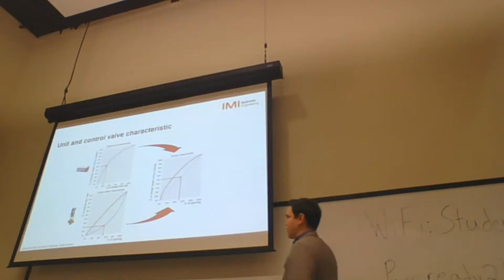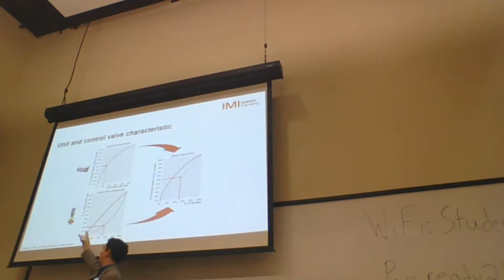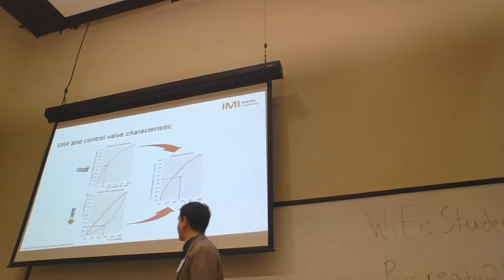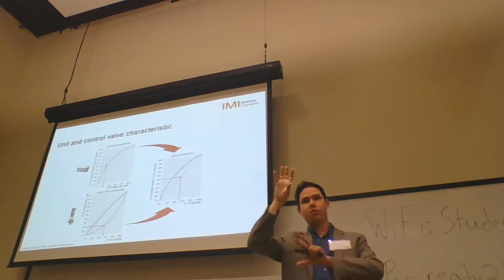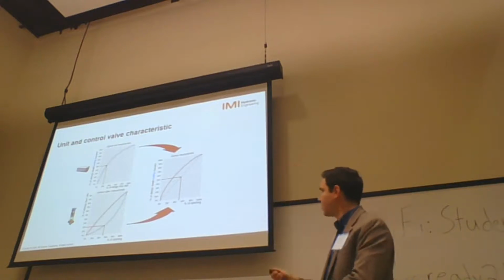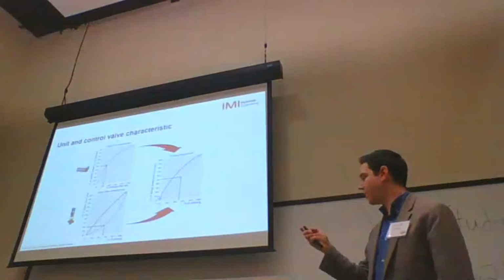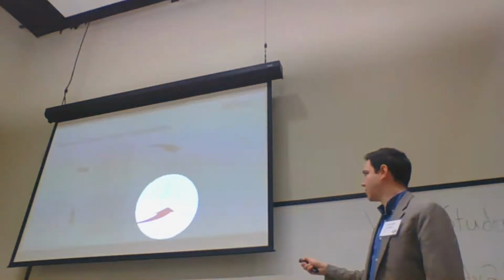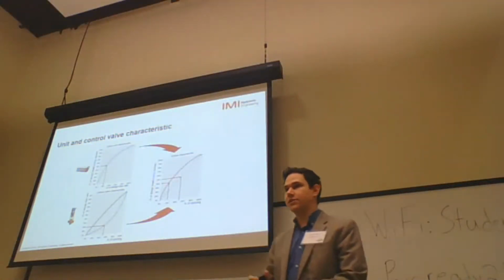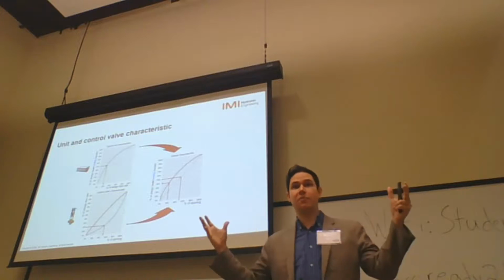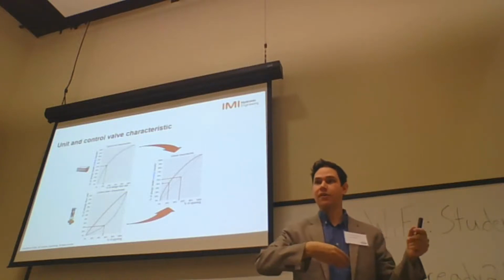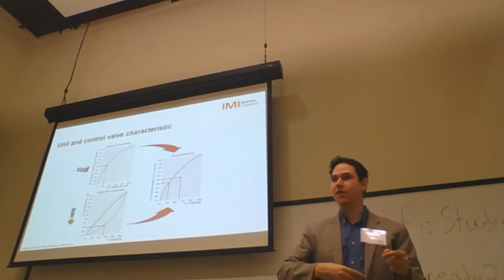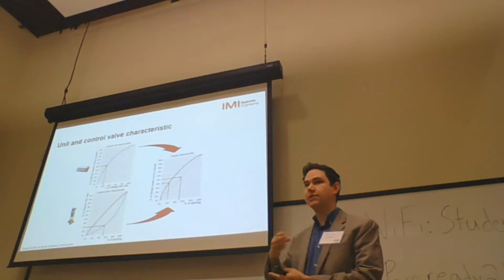When you have it below, there is a distortion in the control valve curve. So instead of the blue, now it's the red one. When you combine the coil with a bad control valve authority curve, the global is not linear anymore. At 20% opening of my control valve, I'm getting almost 40% of the capacity. In other words, with a small opening of the control valve, you're getting a huge capacity on your coil. So the control valve needs to close again, open again, and close again. This is the graphical explanation of hunting in a control valve.